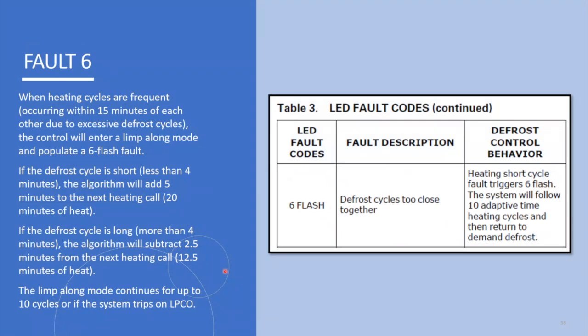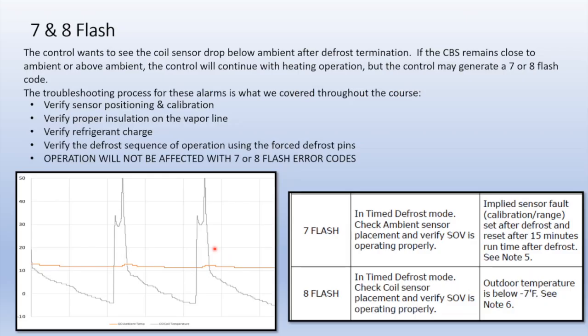6 flash, this means your defrost cycles are too close together. If they're within 15 minutes of each other, often you're going to see a 6 flash associated with low charge. That's usually the biggest reason, because it's not low enough that you're going off on low pressure cutout, but it's low enough that the outdoor coil frosts up very quickly. 7 and 8, this just means that after a defrost, we're not seeing this delta happen. So if you see a 7 or 8, it's not going to affect the operation, but it's going to trigger you to check calibration of both those sensors, the coil and the ambient.